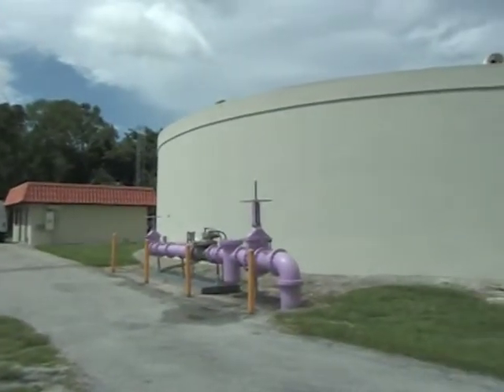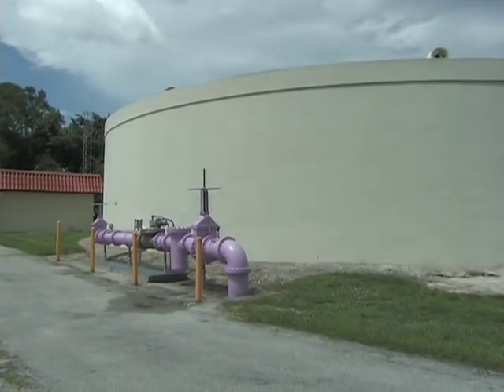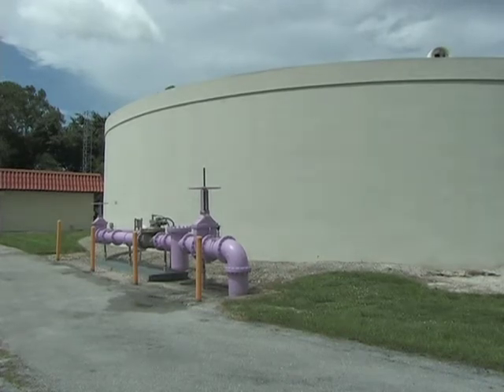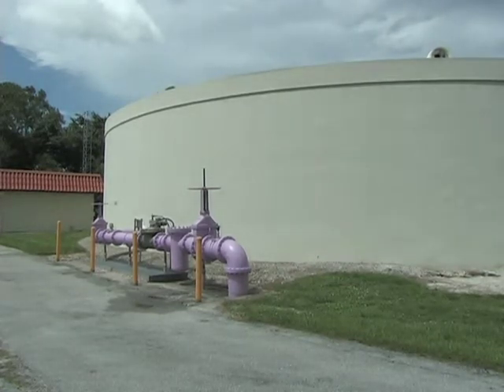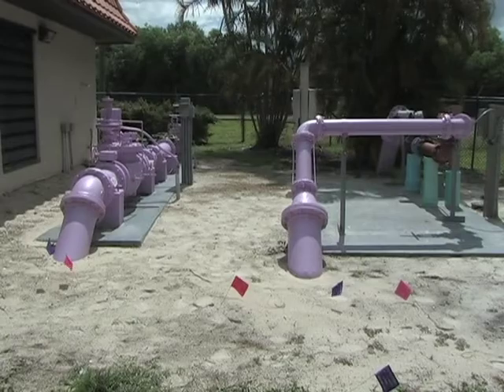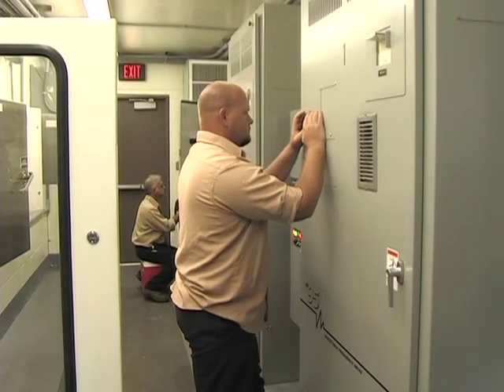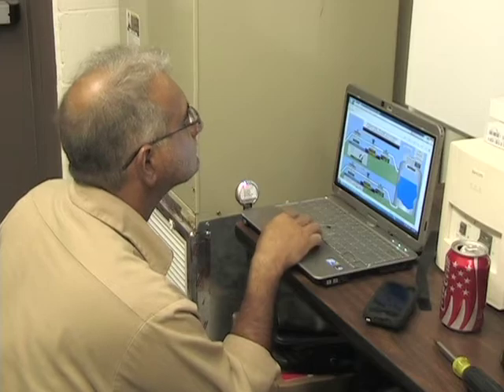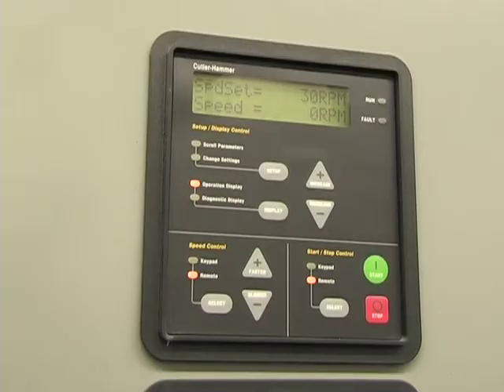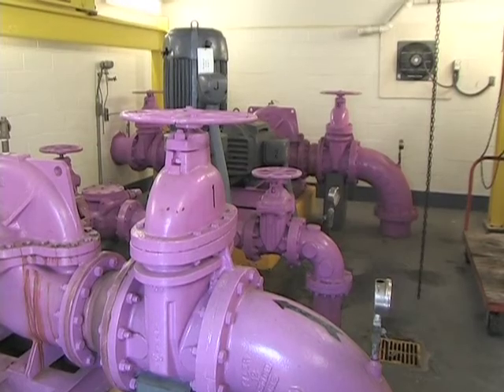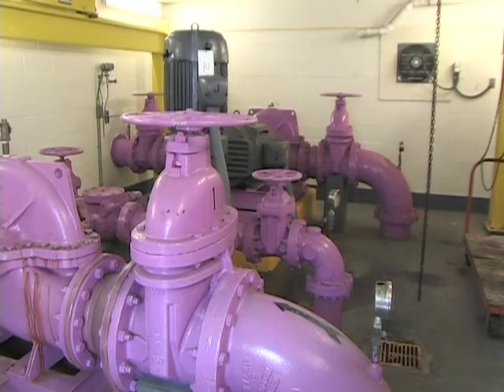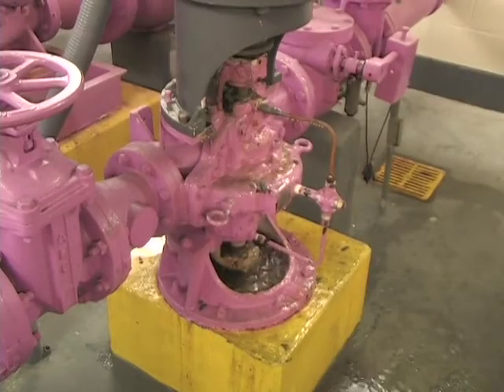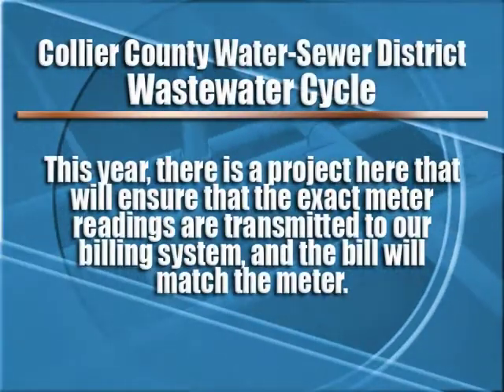The reuse water that is in the ponds at the North Treatment Facility gets pumped to facilities like this. The water is stored in this tank and eventually pumped to golf courses. This electrical equipment and associated meters, valves, and communications devices are aging and becoming unreliable. If failures occur, water may not be measured accurately, or it may not reach the customer at all. This year, there is a project here that will ensure that the exact meter readings are transmitted to our billing system, and the bill will match the meter.